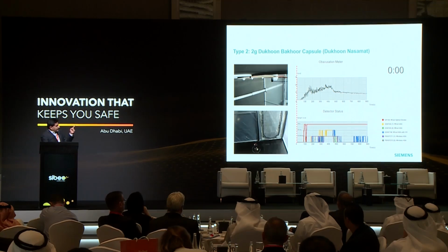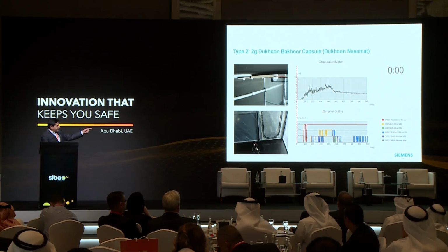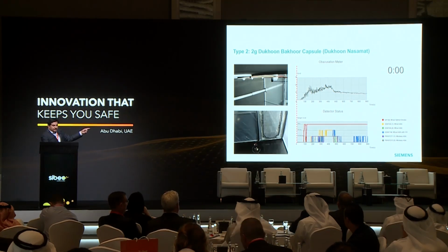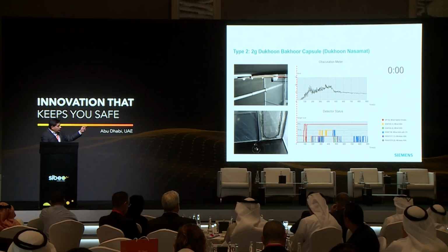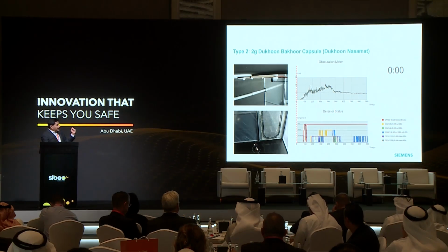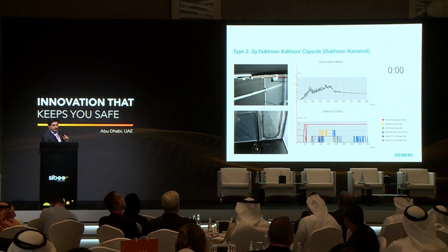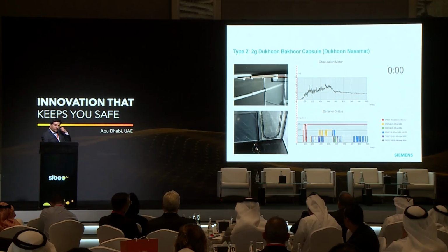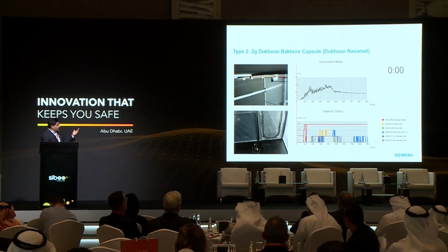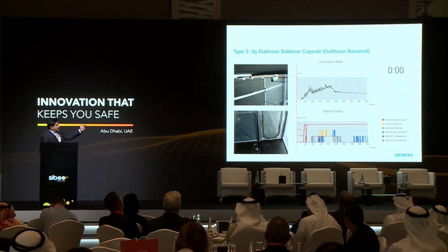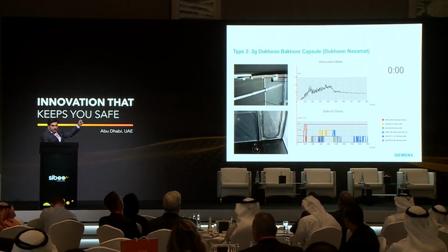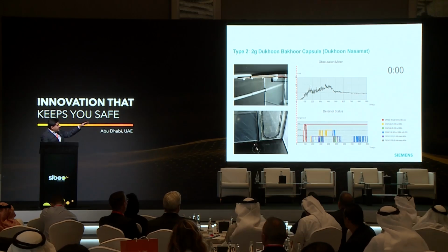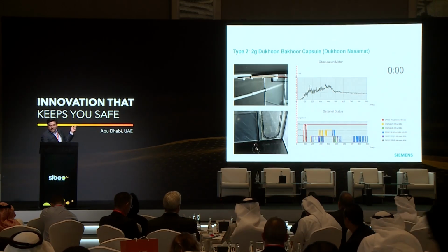So we had regular smoke detectors, and we had the specific ASA technology detectors. The red color indicated on this graph is a regular smoke detector, which is a single optical sensor, and then the yellow, the green, the blue, purple, and the gray are all the ASA technology detectors. Here we have both wired and wireless systems. Also, on the top you see a graph which shows the obscuration rate of the smoke captured during this test that we conducted. So let's play the video.